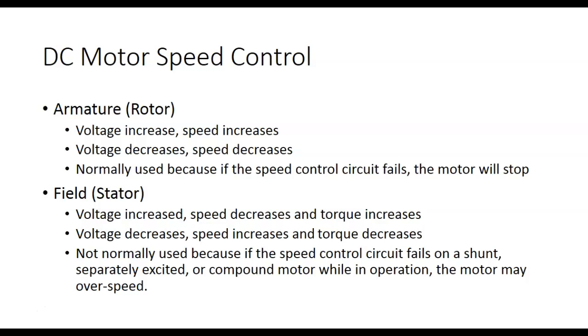We had some 200 horsepower DC motors on the number 4 galvanized line out at US Steel. And that's 200 horsepower, guys. We had one that had an overspeed centrifugal switch on it. It had overspeed connectors, but it slung itself apart 2 times, and we never figured out how it did it.